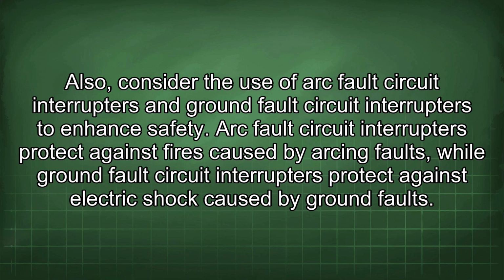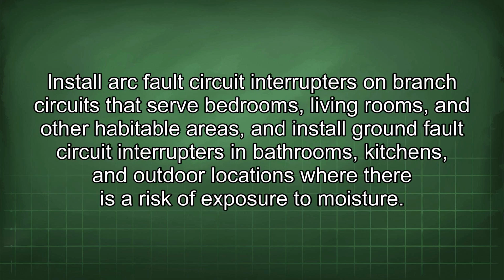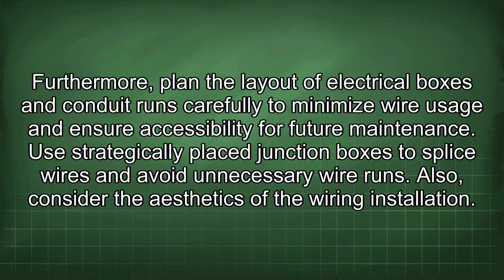caused by ground faults. Install arc fault circuit interrupters on branch circuits that serve bedrooms, living rooms, and other habitable areas, and install ground fault circuit interrupters in bathrooms, kitchens, and outdoor locations where there is a risk of exposure to moisture. Furthermore, plan the layout of electrical boxes and conduit runs carefully to minimize wire usage and ensure accessibility for future maintenance. Use strategically placed junction boxes to splice wires and avoid unnecessary wire runs.